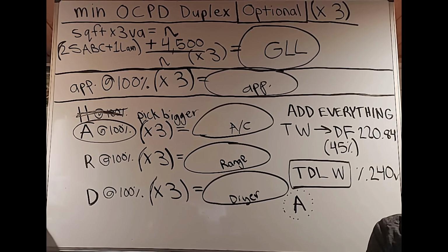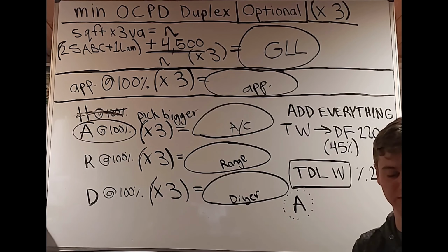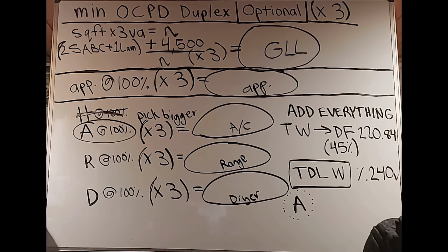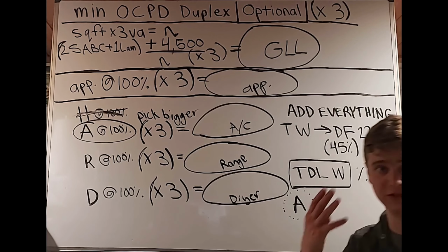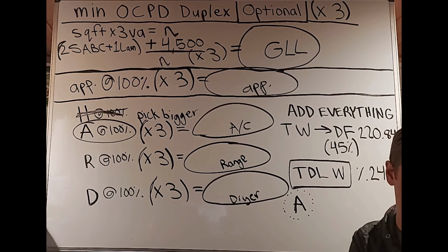Of course, if we land exactly on one of the numbers here in table 240.6a, then we're just going to pick one of those numbers for our answer. The reason why we're doing 800 amps or less sizing up and over 800 amps sizing down is because Article 240.4 Section B tells us to do that. So you could read that and highlight that for yourself. I do explain that in the previous videos.